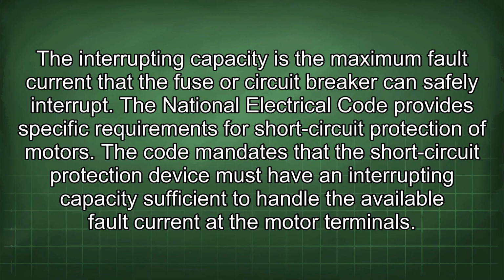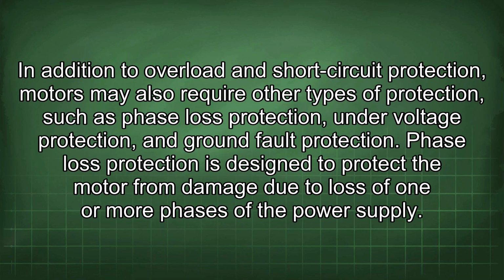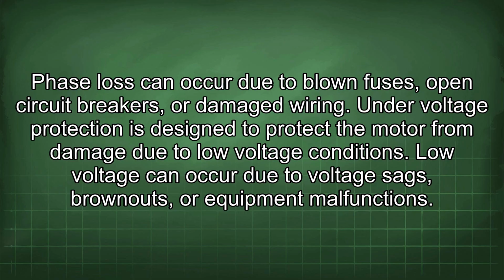at the motor terminals. In addition to overload and short-circuit protection, motors may also require other types of protection, such as phase loss protection, undervoltage protection, and ground fault protection. Phase loss protection is designed to protect the motor from damage due to loss of one or more phases of the power supply. Phase loss can occur due to blown fuses, open circuit breakers, or damaged wiring. Undervoltage protection is designed to protect the motor from damage due to low voltage conditions. Low voltage can occur due to voltage sags, brownouts, or equipment malfunctions.